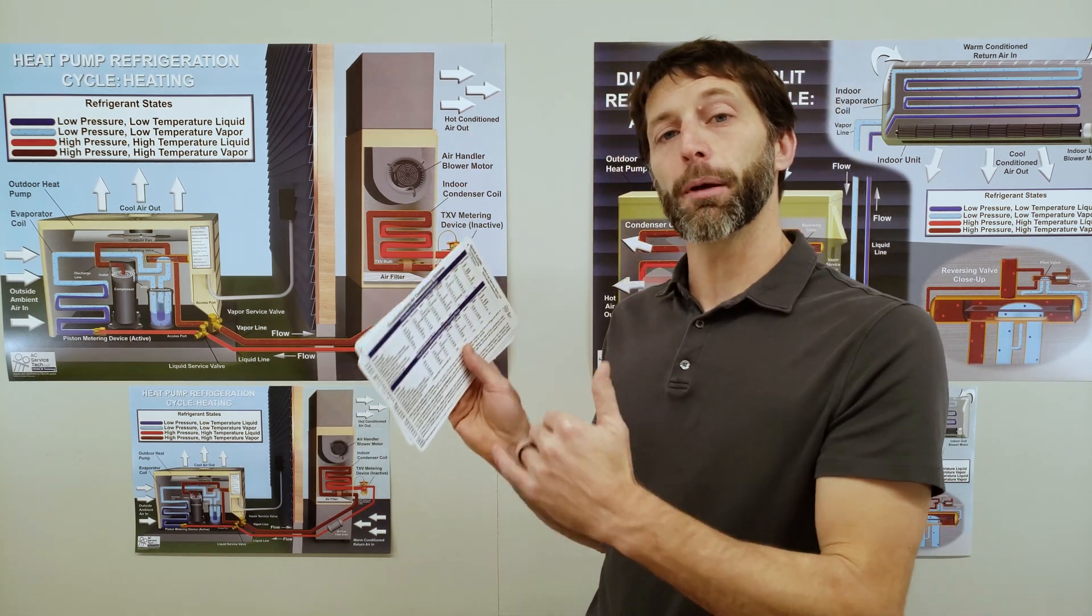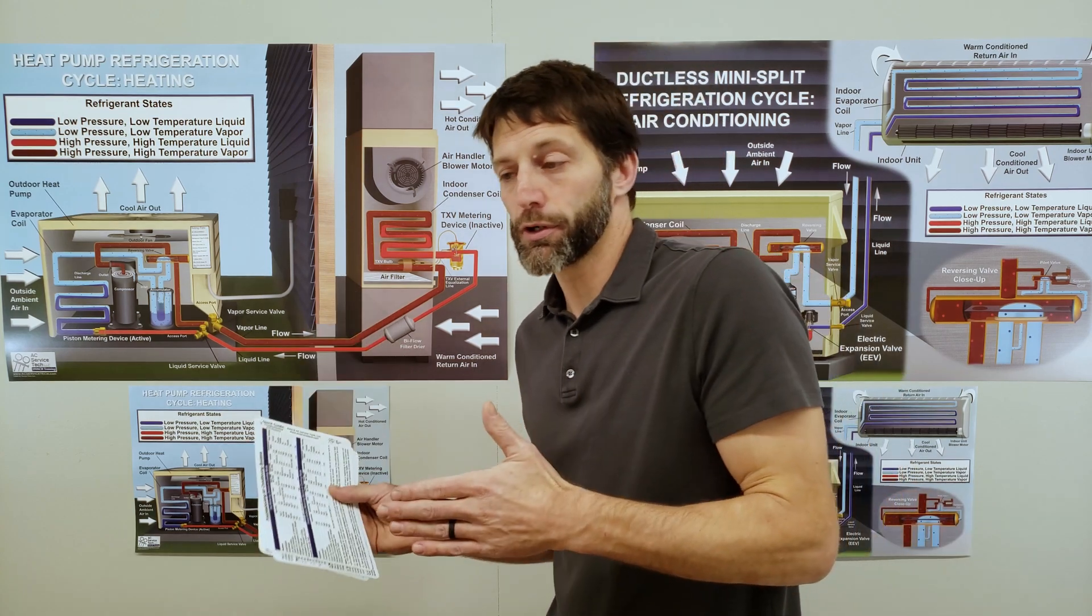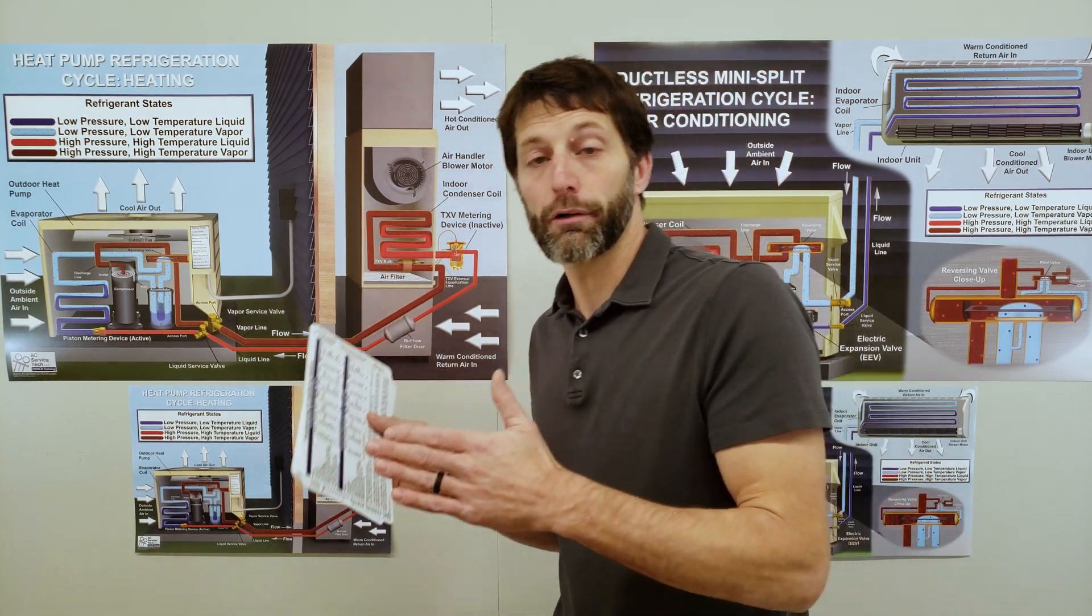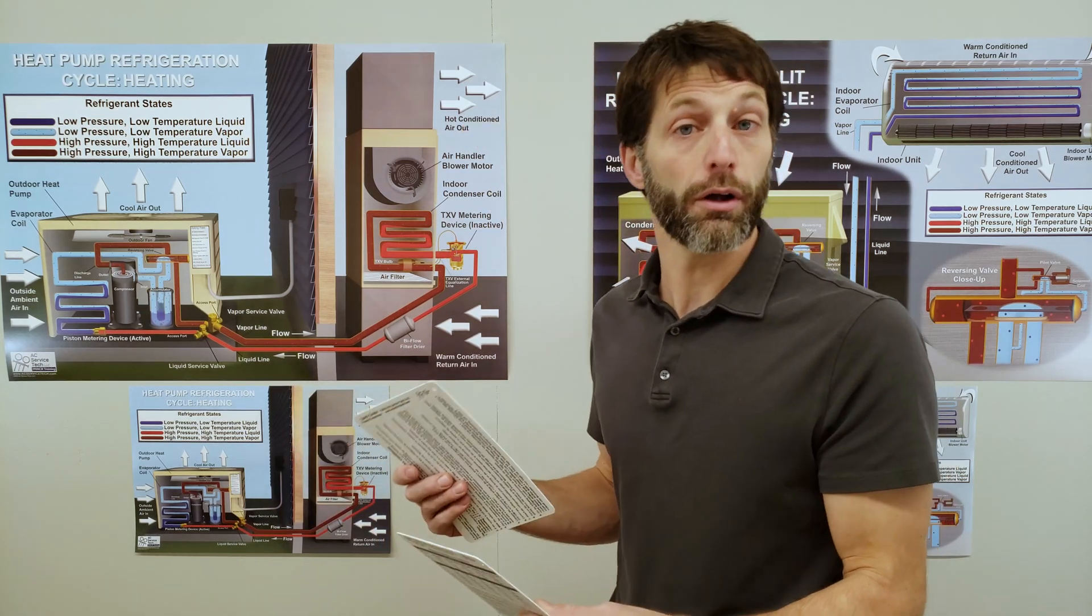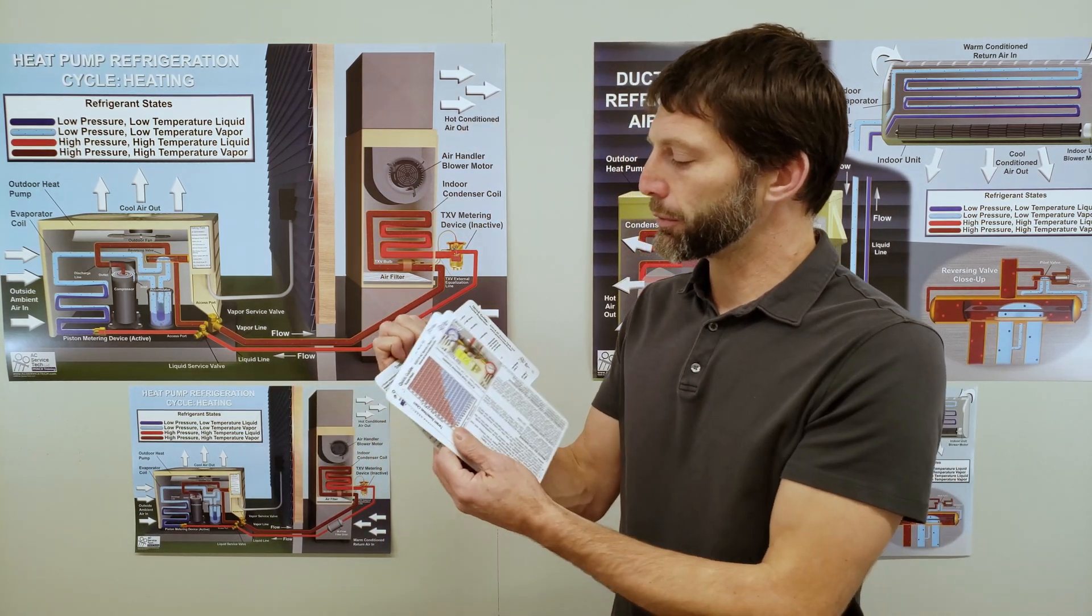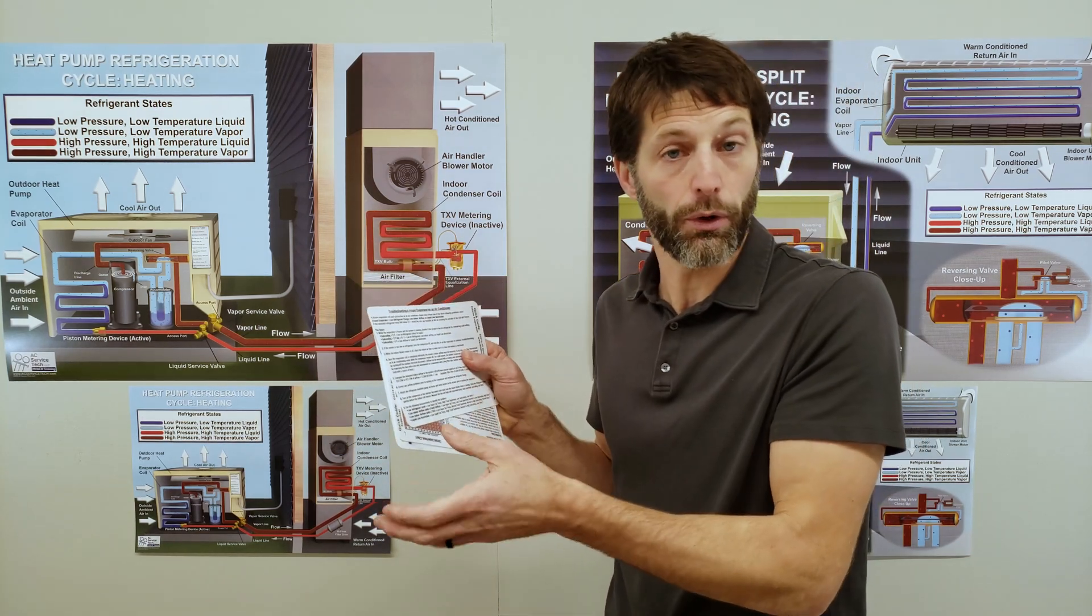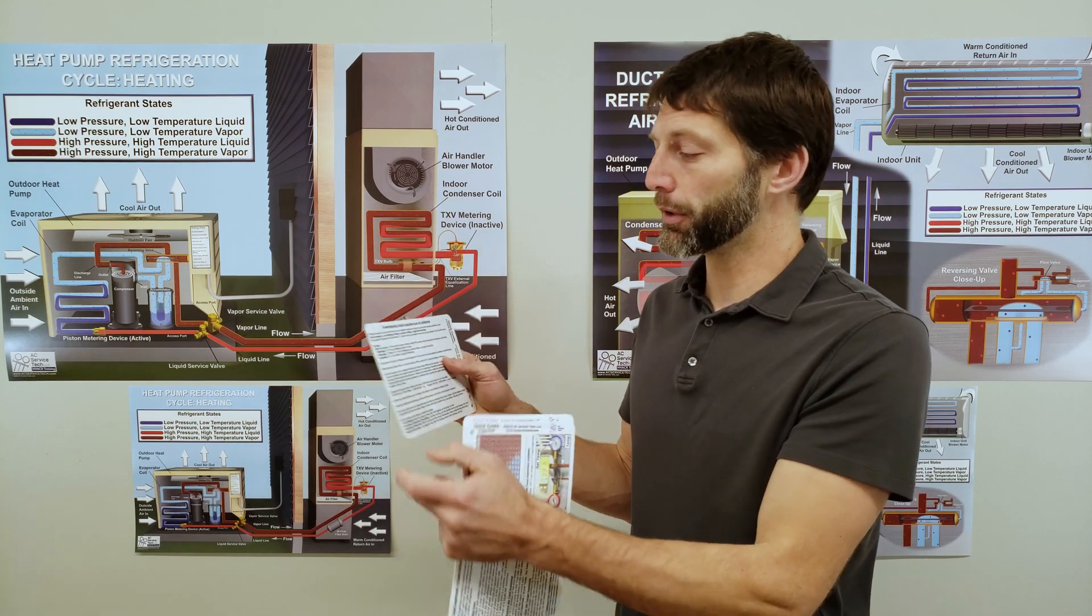So based on that, you're going to be able to tell what the problem is. Are we low on refrigerant? Is the TXV bad? You're going to be able to tell, is it a low airflow problem? So you kind of know where to look. And right here, you have a step by step guide on troubleshooting if there's a frozen evaporator coil.